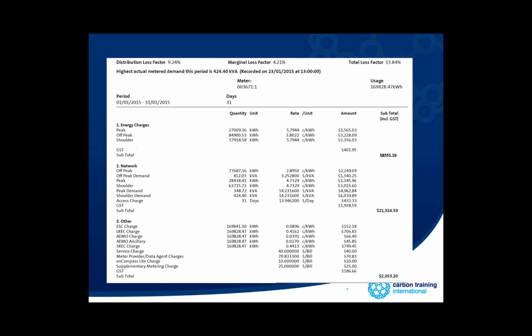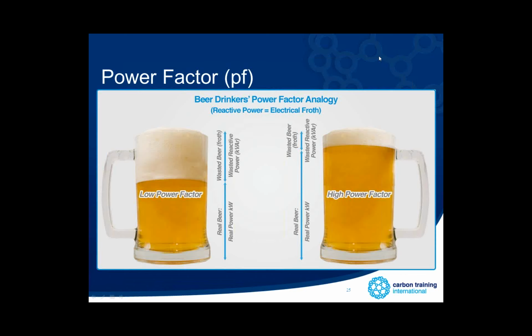Now that is very rarely the case, and in a lot of cases that might be as high as 120 kVA. So to look at this example on this bill, if I've got an inefficient electric motor that's pulling 120 kVA to operate, that's going to cost me an extra 20 kVA charges for that particular period. So we can see that for this bill here, it's $14 a kVA. So for every month, it's going to cost me $280 extra because of that inefficient motor. And that pretty quickly starts to make a business case for doing something about power factor correction. So to look at it a different way, when we look at power factor, it can be compared in a number of ways, where, you know, the beer analogy goes down well with some people.